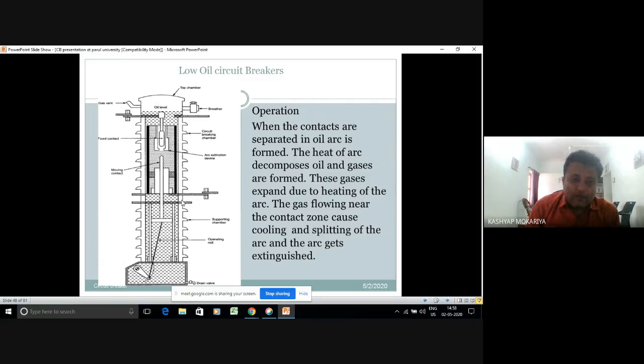Now you can see that when there is a fault and the pressure generated in the oil becomes abnormal, there are chances that your breaker tank can get blasted. So you have this type of gas vent here to take care of that. You can see the chamber here in a low oil MOCB, minimum oil circuit breaker. There is a fixed contact, a moving contact, an arc extinguishing device, and a breather here. Now why is the breather here?